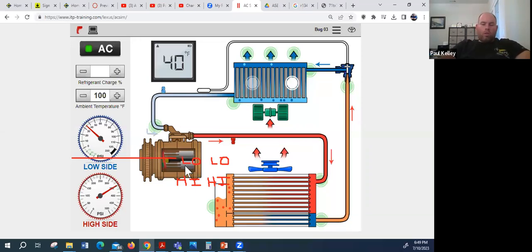Air in the system could also cause the overpressure relief device to vent. So overpressure can cause issues, but it would never cause the compressor to blow up, because first a sensor would fail safe and turn it off, and second the pressure relief device would start to vent it out anyway. That's what's crazy - if it's overcharged, it could actually vent out and get closer to being correctly charged. You'll bring it in and think it's working fine, but there's dye everywhere. What the heck happened? A little bit of a mystery for you.